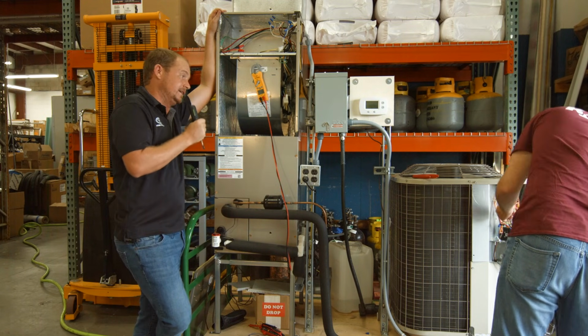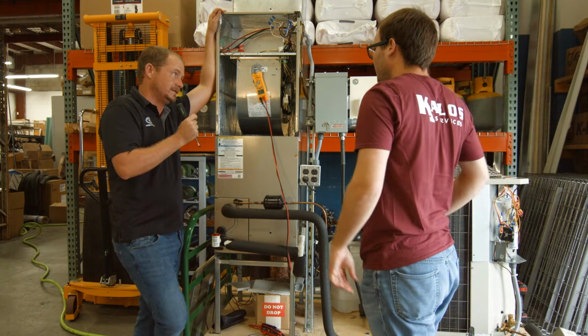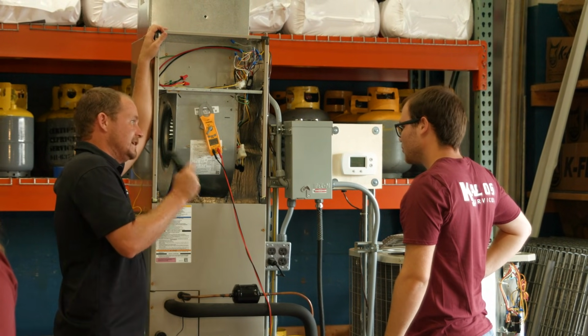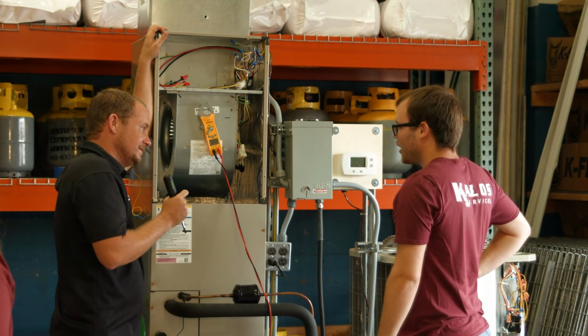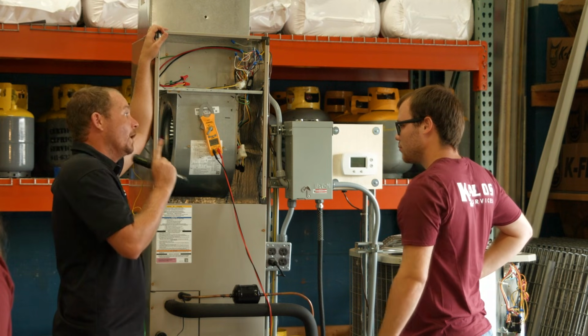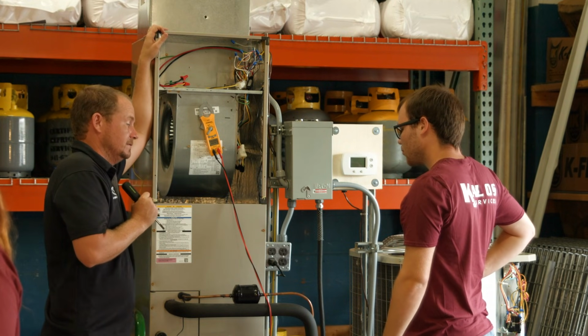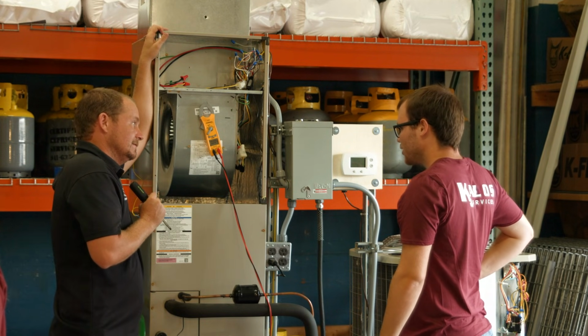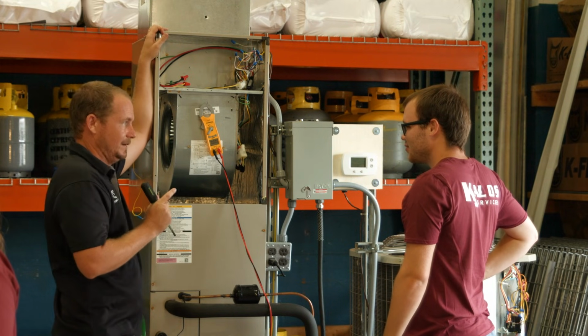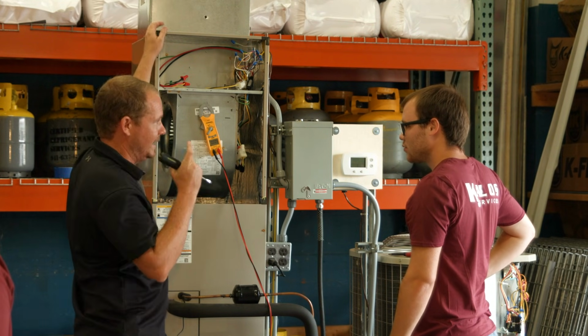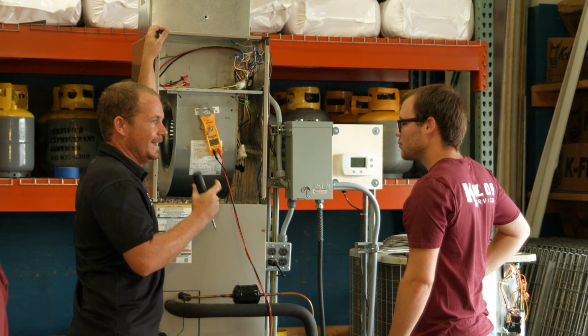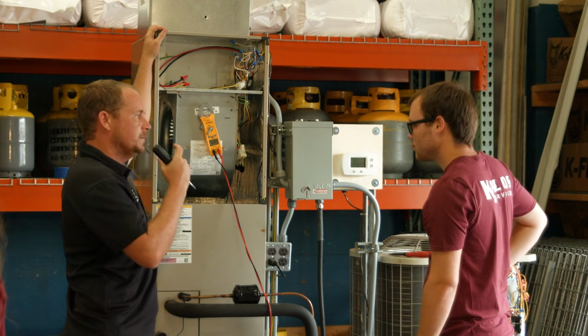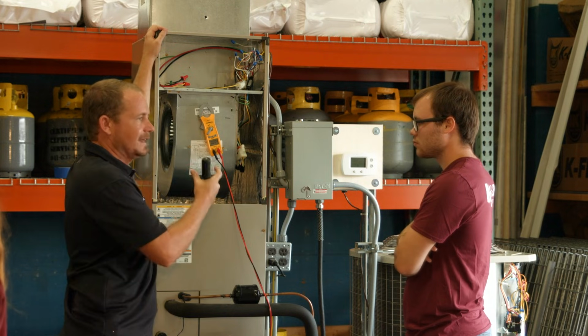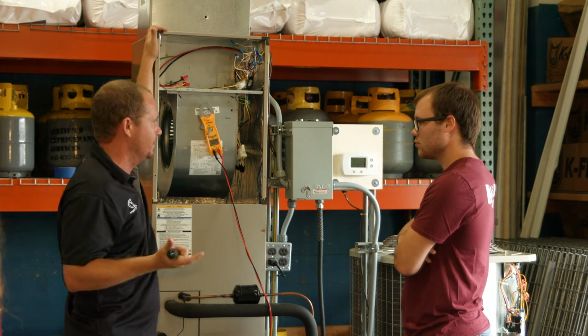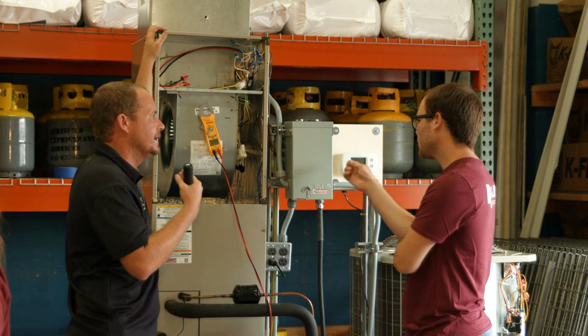That's where that conductor ends, but that's not where the circuit ends, because the O terminal doesn't energize the defrost board. What does it energize? It energizes the reversing valve. But what on the reversing valve does it energize? The solenoid. The solenoid, which is an electromagnet, right? So there's an electromagnet that attaches to the reversing valve, and that's what it energizes. So it could be a lot of different things. It could be that the solenoid is off. It may not be an electrical problem at all, right? So there's a wide range.